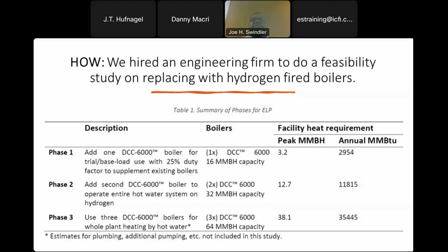So we didn't know much about hydrogen and hydrogen-fired boilers. So we hired an engineering firm to do the analysis for us, and they broke it down into 3 phases. The first phase would be replacing one gas-fired boiler, and then the second will be 2 and 3. And you can see the peak MMBH there, they calculated for us, and how much natural gas in million BTUs we would need to replace our gas-fired boilers with hydrogen-fired boilers. This is for the East Liberty plant only.